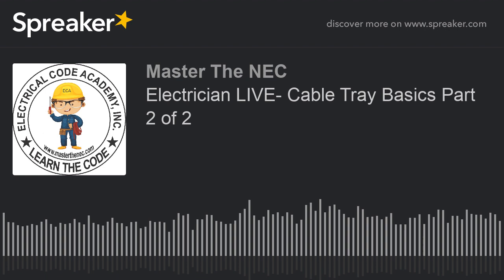digest it. So 392.80(A)(3) says combination of multiconductor and single conductor cables. Where a cable tray contains a combination of multiconductor and single conductor cables, the ampacities shall be as given in 392.80(A)(1) for multiconductor cables. So we do just what we did anyway. We don't do anything special. We treat it the same way we just calculated a minute ago for that.